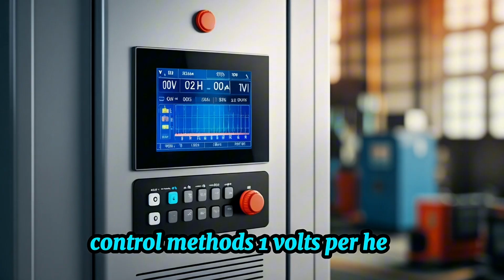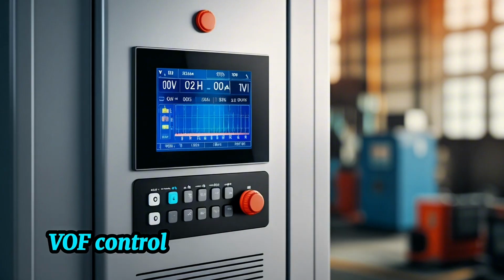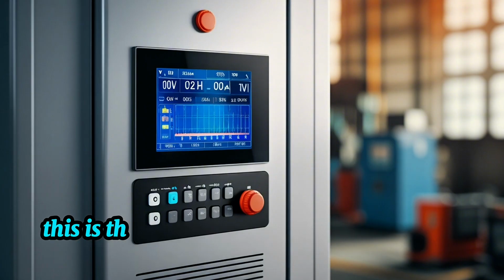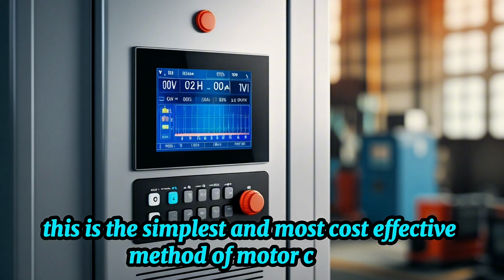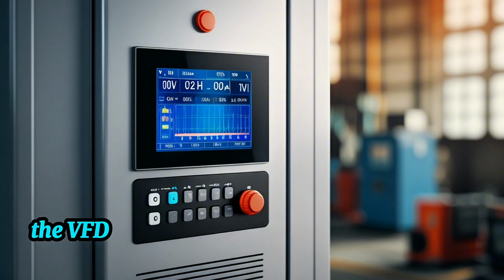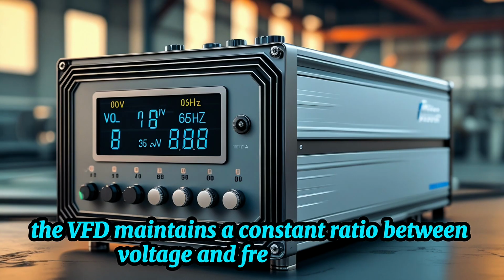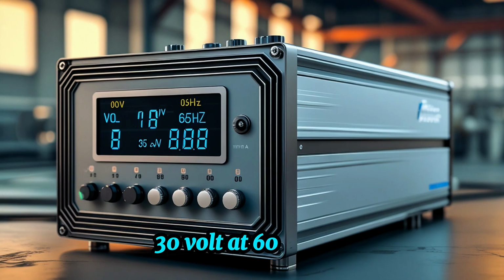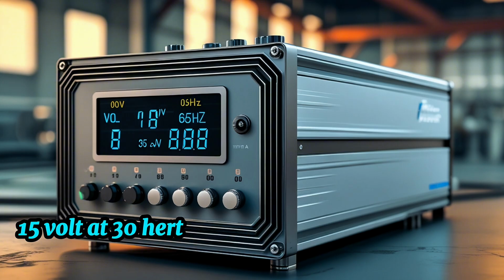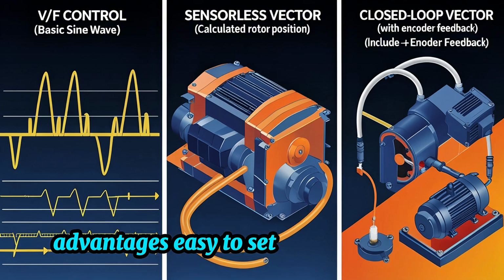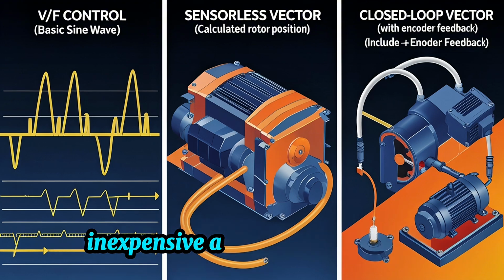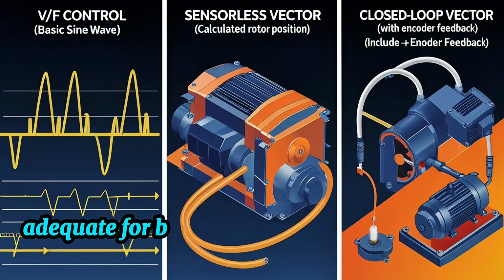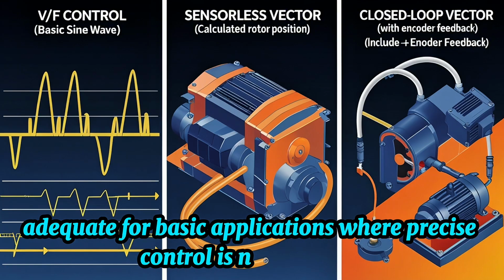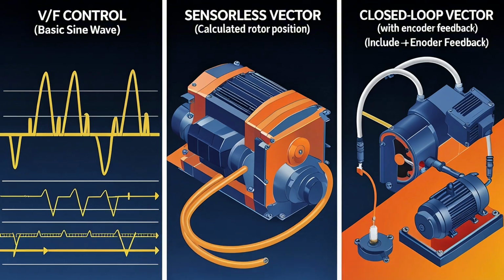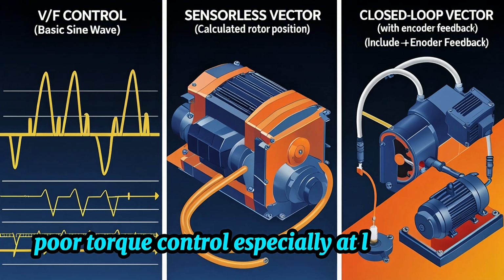1. Volts per Hertz, V/F, control. Also known as scalar control, this is the simplest and most cost-effective method of motor control. In this approach, the VFD maintains a constant ratio between voltage and frequency, e.g., 230 volt at 60 Hz, 115 volt at 30 Hz, to keep the magnetic field in the motor stable. Advantages: easy to set up and configure, inexpensive and widely available, adequate for basic applications where precise control is not essential. Limitations: poor torque control, especially at low speeds.